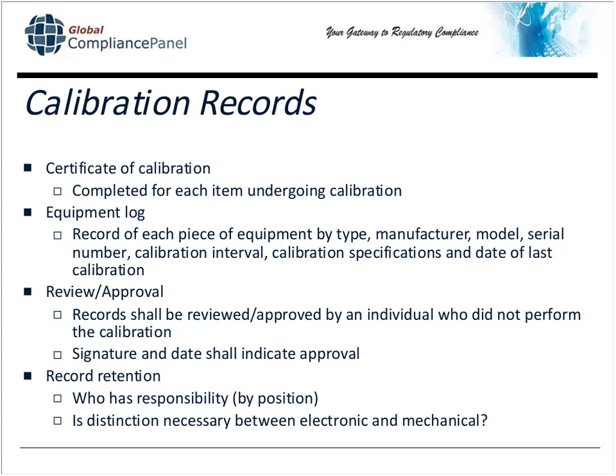There are a lot of data points that need to be recorded to assure that you calibrate on schedule and the same way each time. For any internal certificates of calibration that you prepare, you want someone to review and approve them, someone who did not perform the calibration. It's a good internal check. In my experience, the FDA inspector realizes that the reason you're performing calibration in-house is, quite honestly, to save a few dollars. So even though you have external standards used and you have everything covered, a second set of eyes on an internal process that's normally outsourced is usually a good idea.